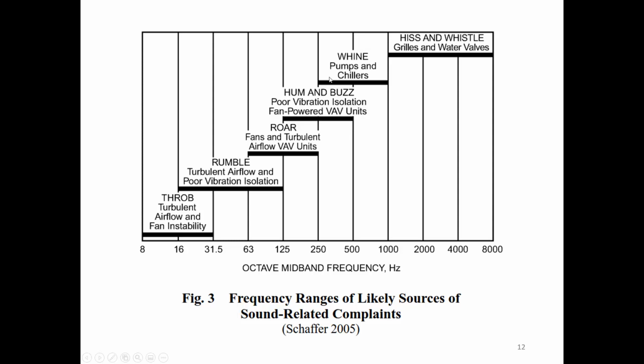Whine - pumps and chillers produce a pretty tonal, annoying whine. Sometimes chillers put this in the 250 to 1000 hertz range, maybe more around 125. Sometimes that tone is more in here, and the airspace mass resonance of windows will let it through.